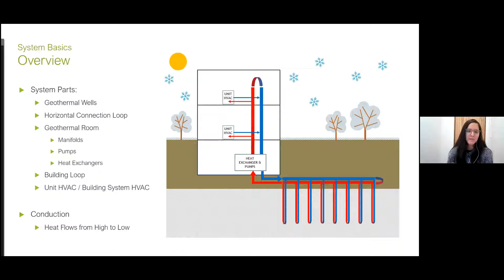In winter, let me get the pointer out, might be helpful. So in winter, what's happening is we have heat from the ground moving into the loop. When it then goes up into the building, it's then pumped into the building loop, and each individual HVAC unit that's tied to that building loop will pull heat out of it. The heat pump within the unit will then expel that heat to the space.